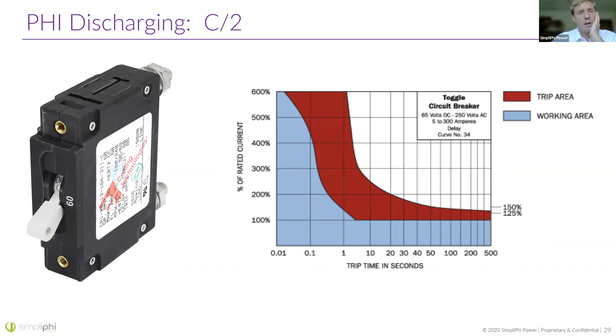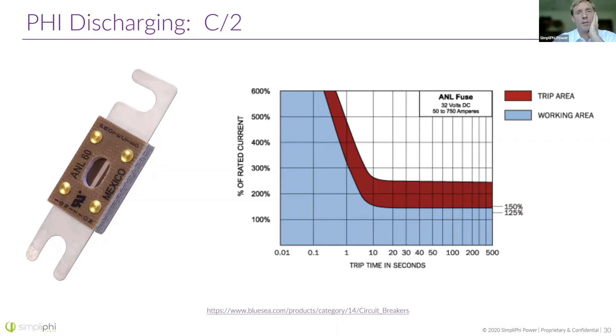So there's a lot of variation in the breakers themselves and in the specifications of the breaker. So just keep that in mind as you're sizing a system. Again, this is a fuse, and this fuse is telling you, okay, at 150% of the rated capacity, which would be 90 amps for this fuse, it's still going to take 10 seconds to trip. Probably wouldn't damage the battery if you had that in and you had the fuse sized properly. But these are considerations to make if you're going to put breakers, DC breakers and fuses into your system.